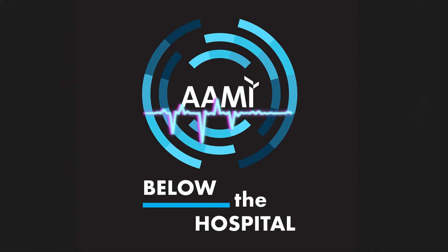And last but not least, inspect before storage and before use. Event-related sterility depends on package integrity over time and handling events. And if you need something to go to, for the listeners, AAMI ST79 steam sterilization guidance reinforces everything I just said. From drying, packaging, loading, and storage, they're all linked. You cannot fix a system problem at just one step. Thank you for calling that out, just in case anybody wanted to say, well, that's Dr. Brown saying that. No, ST79 calls it out.